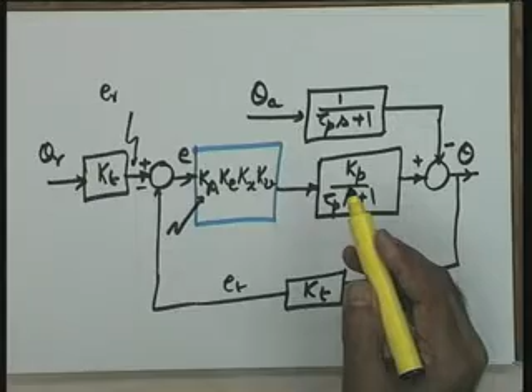Okay. So, you put 4 different blocks in your diagram and you get the complete functional block diagram of this system. You will please note Ka has the units voltage on one side, voltage on the other, Ke voltage on one side, pressure on the other, Kx pressure on one side, displacement on the other, Kv displacement on one side and the steam flow rate on the other side. I hope this is clear. These are the 4 basic units.